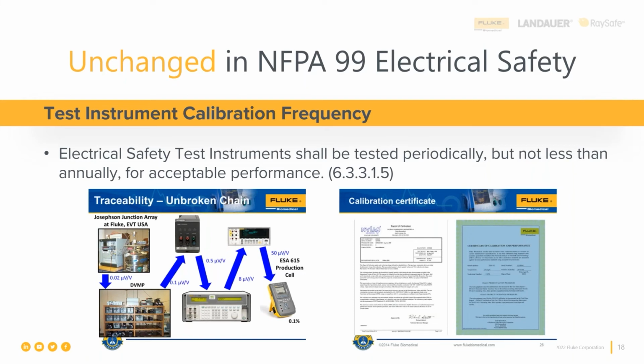Moreover, if it's discovered that your test is out of tolerance, you will need to go back and repeat every test you did from the last acceptable cal verification to this current one where you were out of tolerance. So annually is a requirement under the NFPA 99. So don't be fooled. Make sure you understand what's in there.